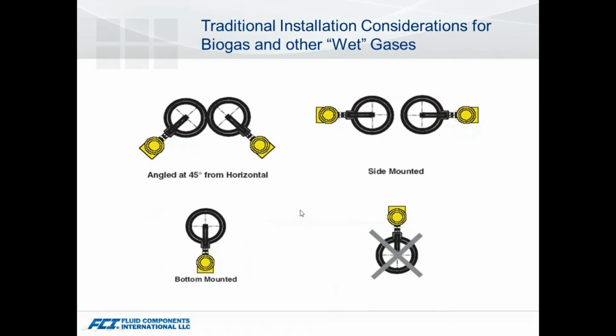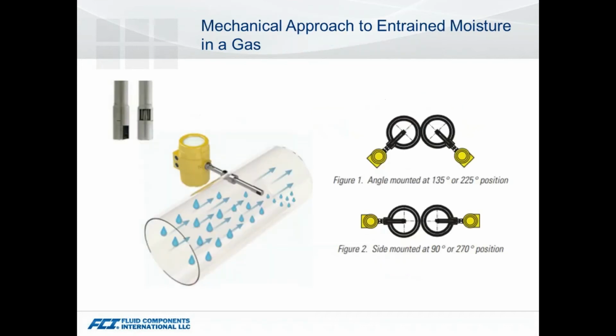So traditionally, we've had other ways to address wet gas, such as just your mounting orientations, and this would apply to any of our meters. For moisture, we prefer to be in that lower half of the pipe, whether it's side, 45, or bottom. When you have it on the top, all you're doing is giving a flow path for any condensation that might form on the wall of the pipe to flow down to the sensor itself. And that's a situation we want to avoid.